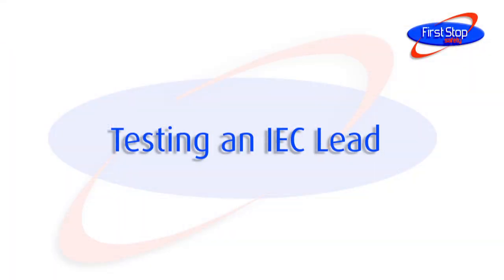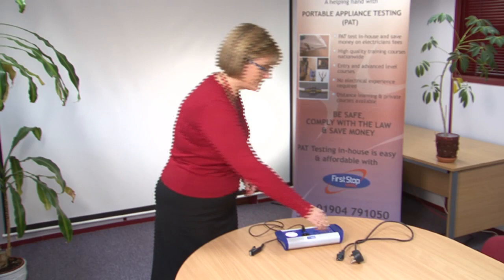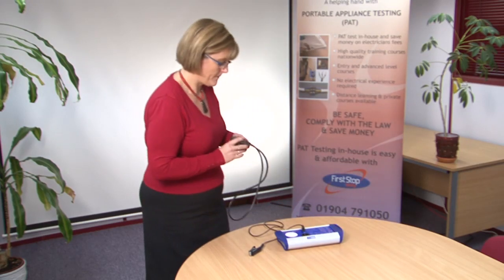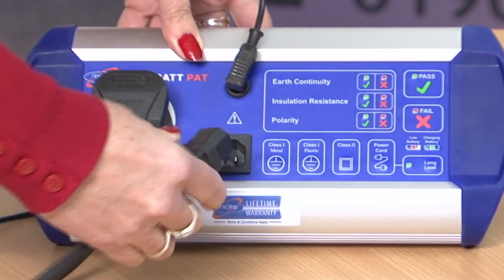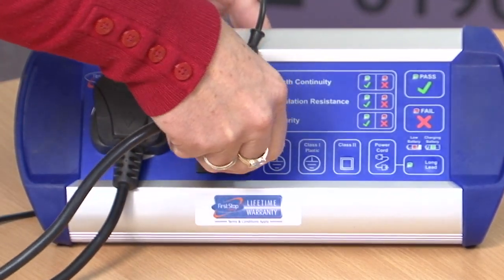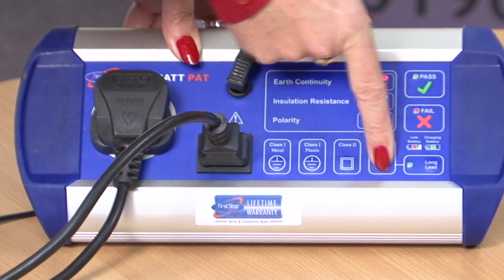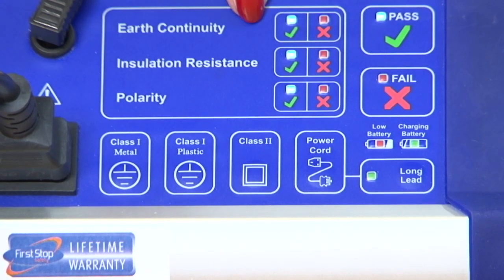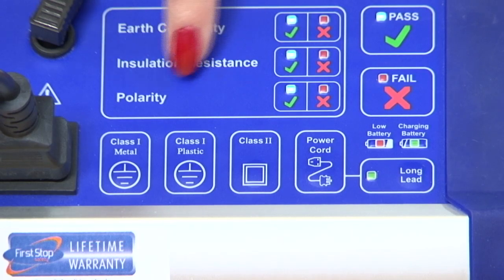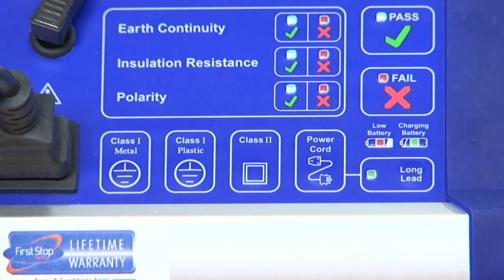Testing an IEC lead. Plug both ends of the IEC lead into the tester and press the power cord button. The Watt PAT carries out the test and displays the results of the earth continuity, insulation resistance and polarity tests. The polarity test checks the lead is wired correctly.